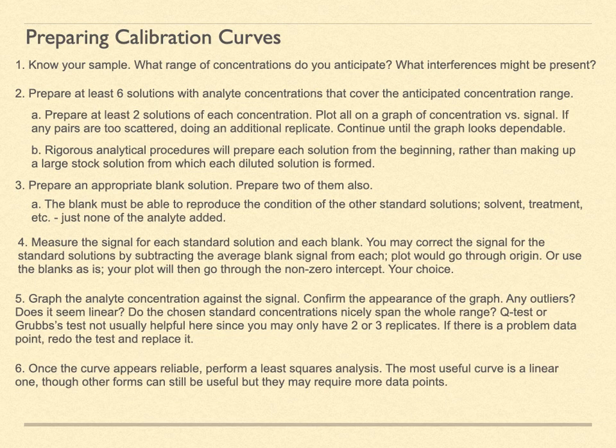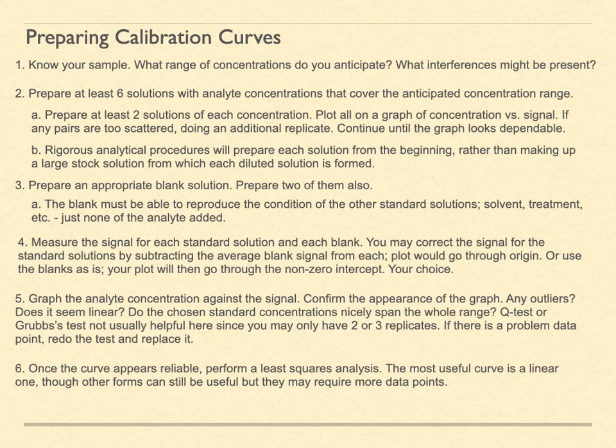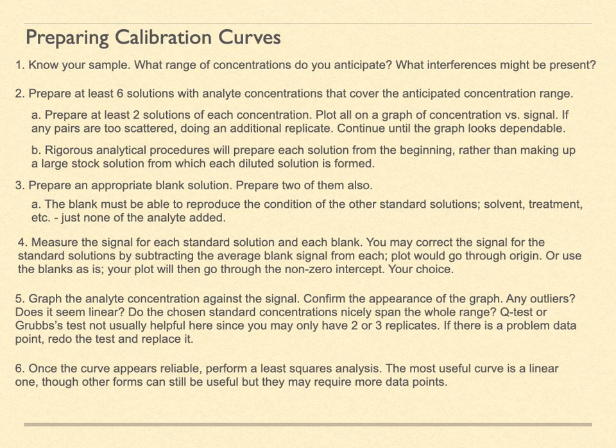Graph the data as analyte concentration versus signal. What does it look like? Are there any outliers? Does it seem linear throughout the range? Does the curve lead to a good fit of the data? And finally, perform a least squares analysis on the data. Hopefully, it fits well to a linear response. But if not, a higher order polynomial or an exponential or logarithmic model may fit better. Experience and knowledge about your analytical experiment can guide your choices. Much of what we will be doing will be with linear models.